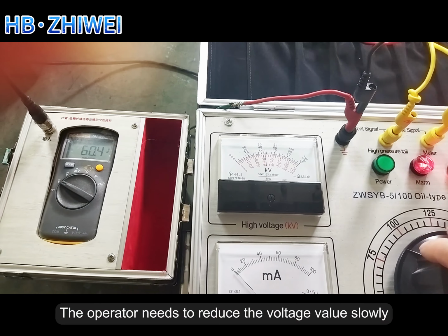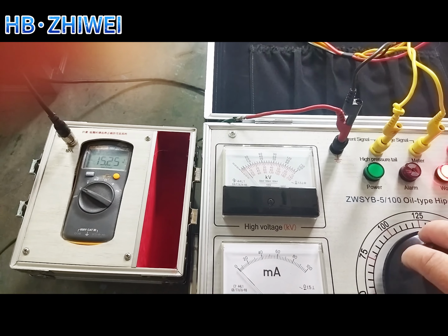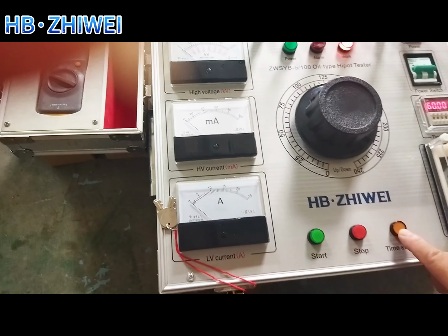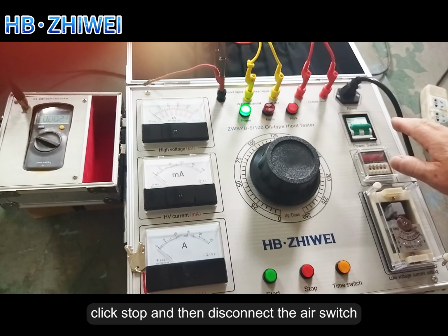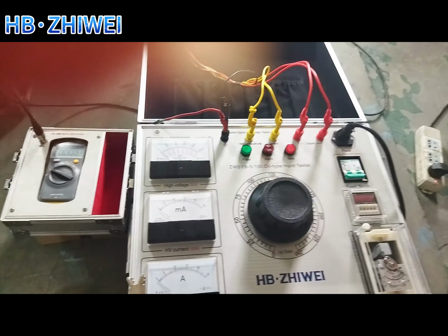The operator needs to reduce the voltage value slowly. Do not reduce the voltage quickly. Click the timer switch again, click stop, and then disconnect the air switch. The test is over.